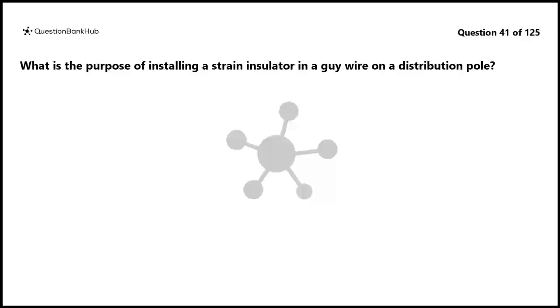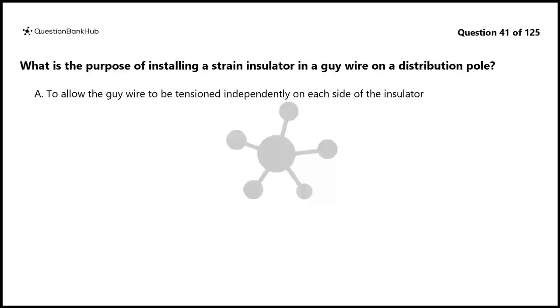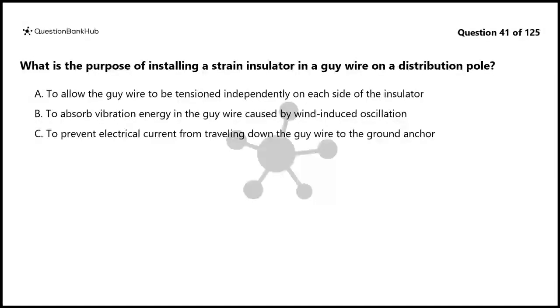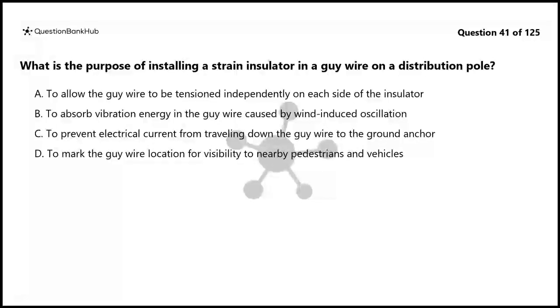Question 41. What is the purpose of installing a strain insulator in a guy wire on a distribution pole? A. To allow the guy wire to be tensioned independently on each side of the insulator. B. To absorb vibration energy in the guy wire caused by wind-induced oscillation. C. To prevent electrical current from traveling down the guy wire to the ground anchor. D. To mark the guy wire location for visibility to nearby pedestrians and vehicles.